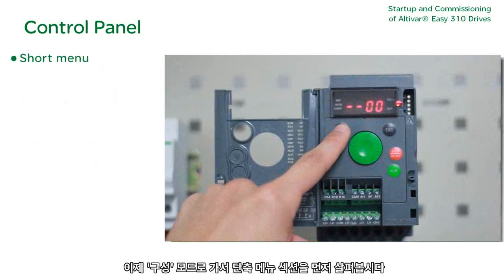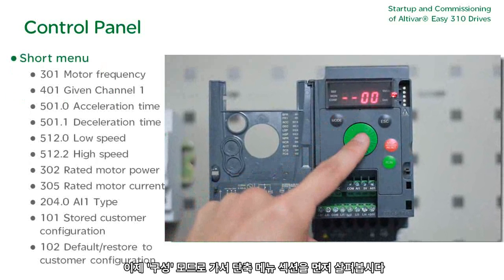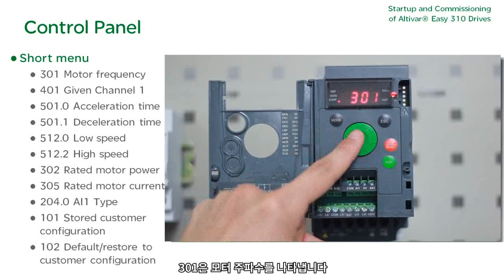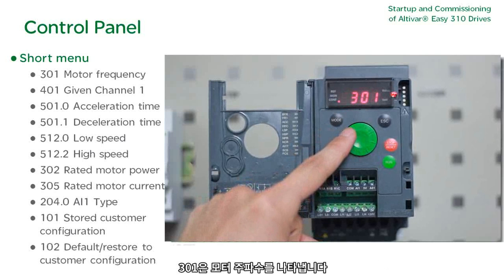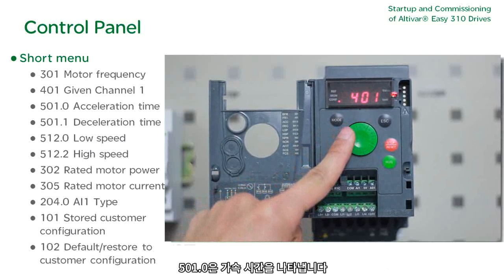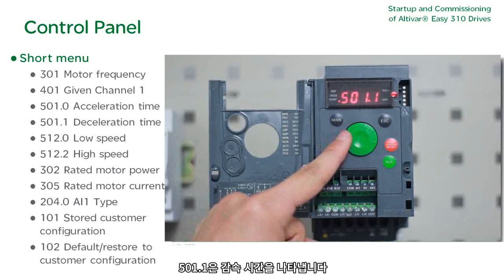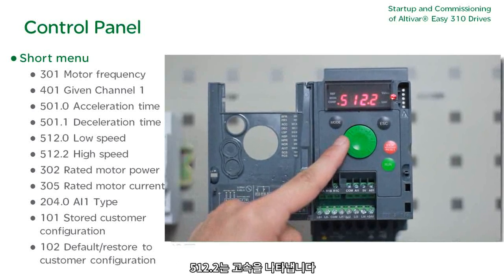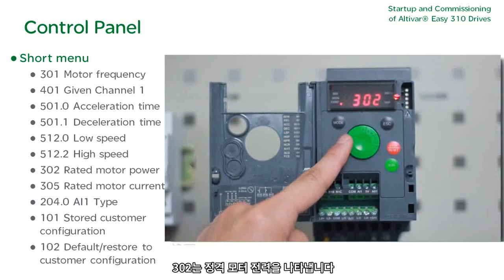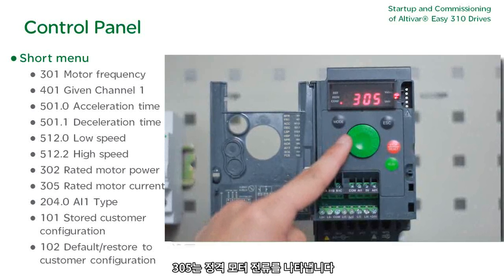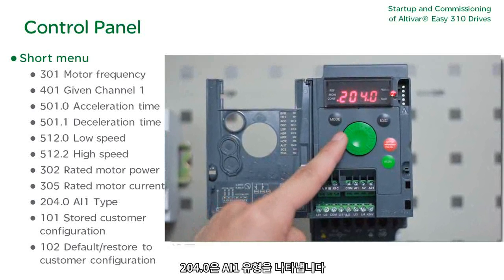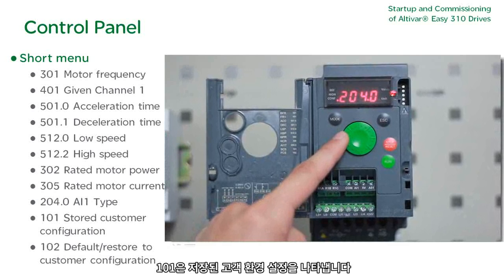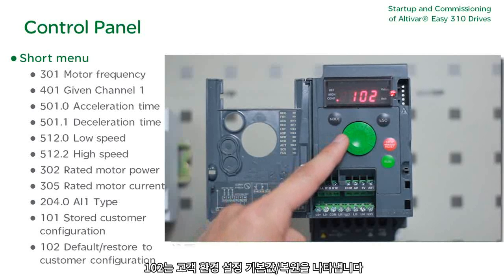Let's enter configure mode. Configure mode first displays the short menu section: 301 is motor frequency, 401 is given channel 1, 501.0 is acceleration time, 501.1 is deceleration time, 512.0 is low speed, 512.2 is high speed, 302 is rated motor power, 305 is rated motor current, 204.0 is AI1 type, 101 is stored customer configuration, and 102 is default restore to customer configuration.